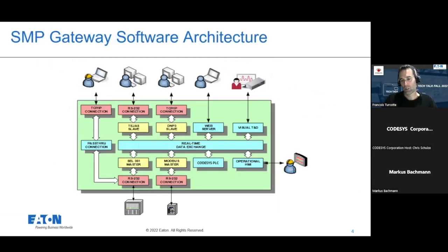So what's the architecture of the SMP gateway? That's just a very simplistic representation of what's inside the SMP gateway and how we interact between all of the modules. The first thing I'll discuss is the implementation of masters, and what we call master and slave. A master is a module we use to communicate and pull information from an IED in the substation. So a master can interact with an IED in TCP. It can interact with RS-232. So there are different types of media or communication you can use with a master to collect information from the field.